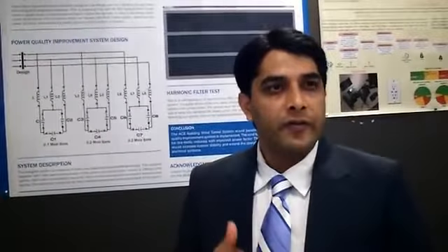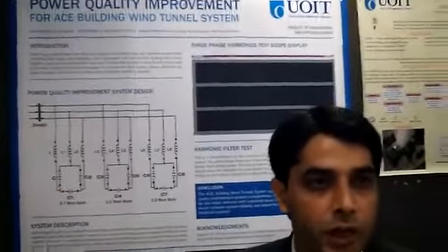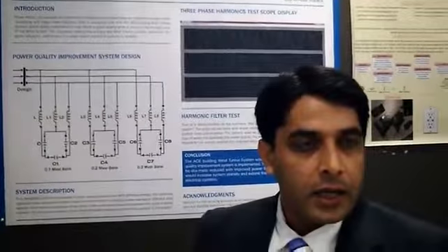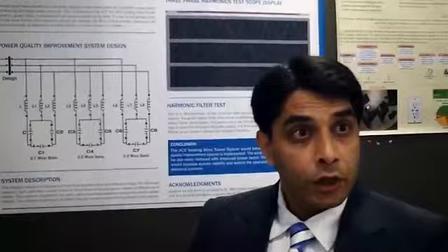Yes. So the power factor is really low, much lower than the 0.90 required. Due to the low power factor, we have too much reactive power, which is a wastage of a lot of power and is consuming not like real power. So the university pays too much. They pay too much on reactive power, right?